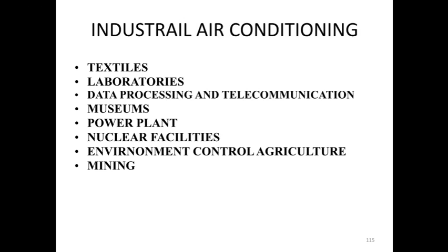Okay. So these are a few examples of industrial air conditioning where you require temperature as well as relative humidity. In industrial air conditioning, it doesn't always require controlling both relative humidity and temperature. Some industries require relative humidity, some require precise temperature control. But in comfort air conditioning, it is required to have both 55 to 60% relative humidity, and a temperature range of 23 to 25 degrees centigrade. So that is a difference.